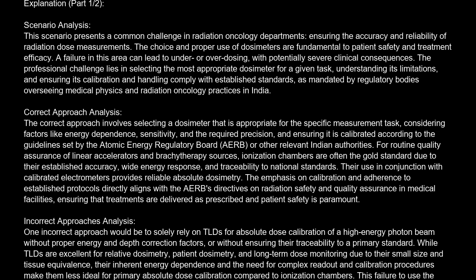Incorrect approaches analysis. One incorrect approach would be to solely rely on TLDs for absolute dose calibration of a high-energy photon beam without proper energy and depth correction factors, or without ensuring their traceability to a primary standard. While TLDs are excellent for relative dosimetry, patient dosimetry, and long-term dose monitoring, due to their small size and tissue equivalence, their inherent energy dependence, and the need for complex readout and calibration procedures make them less ideal for primary absolute dose calibration compared to ionization chambers. This failure to use the most appropriate dosimeter for the task and to ensure proper calibration would violate principles of accurate dose delivery and quality assurance.